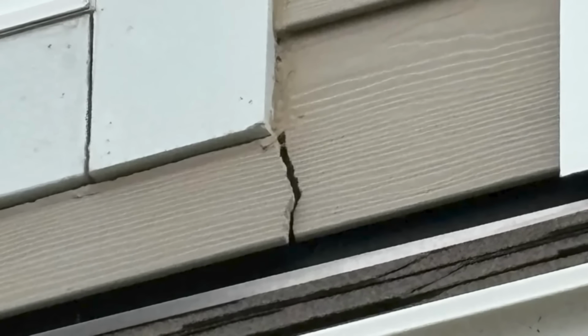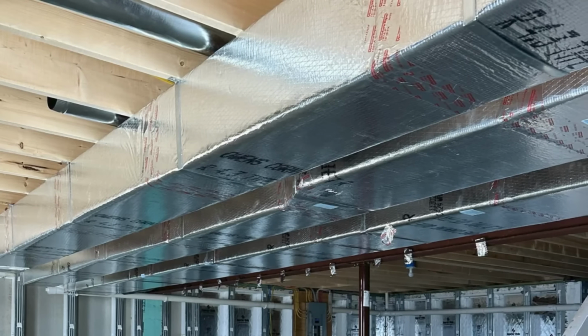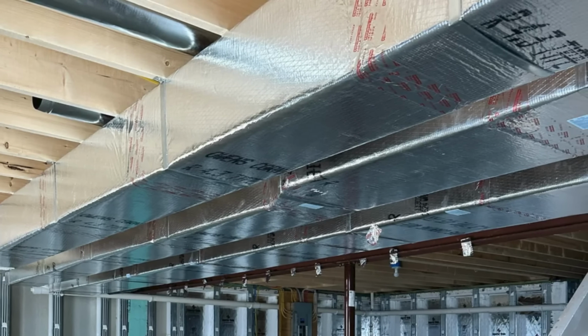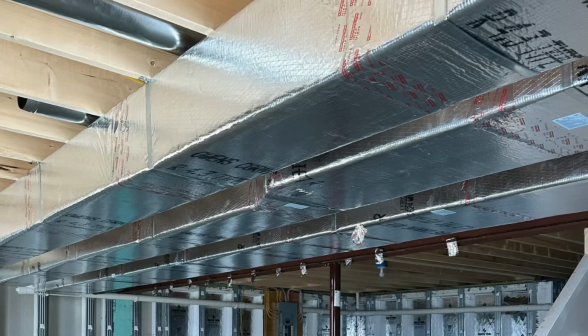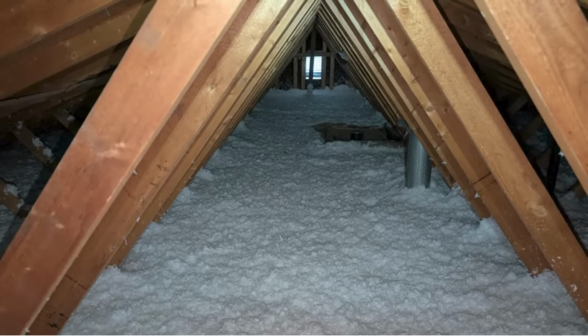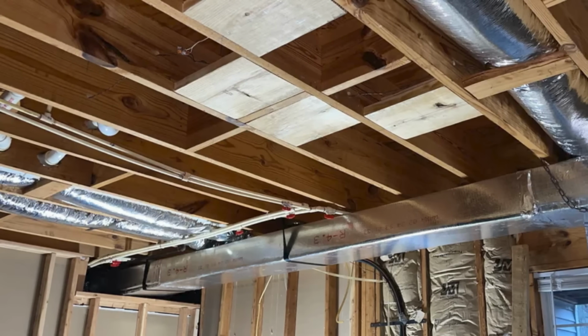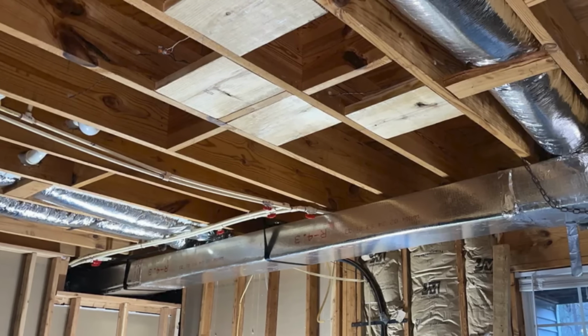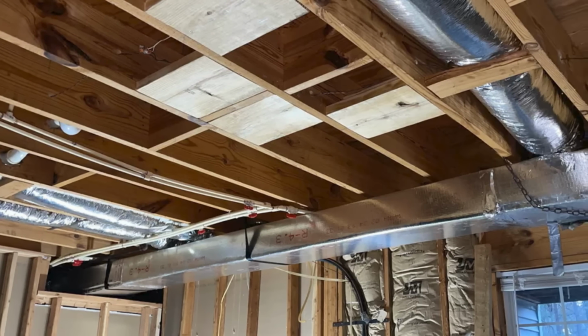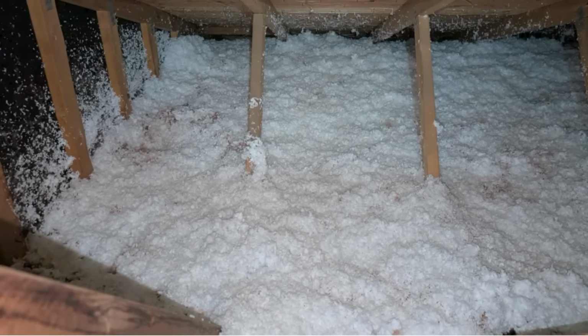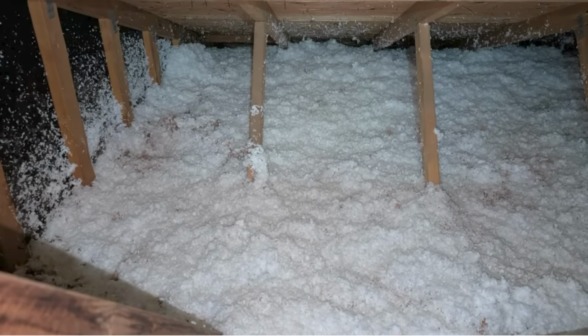So, how do we solve this? The best practice approach is to locate your entire air distribution system and air handling unit inside the home's conditioned space with the vented attic above. This means your ductwork must be located below the attic's air barrier and within the interior pressure boundary. The only thing that should be in this type of attic is insulation on the attic floor.